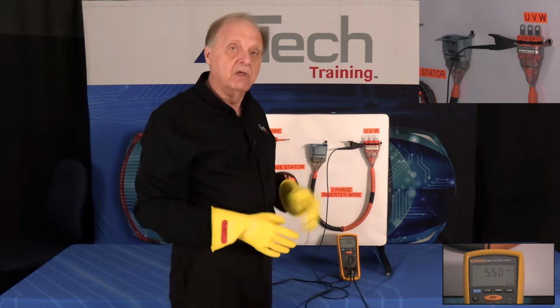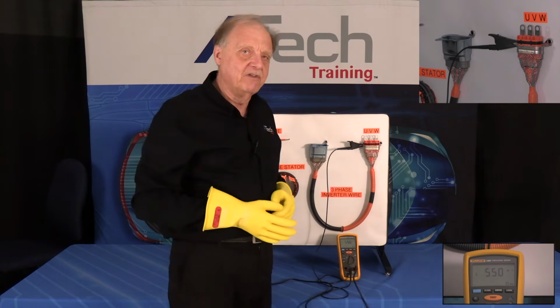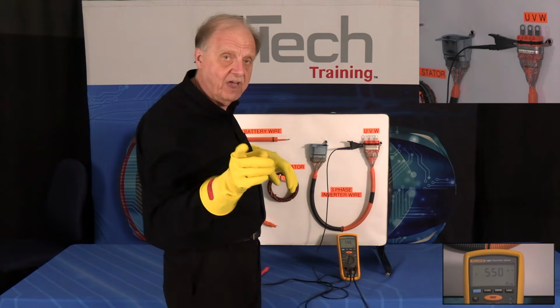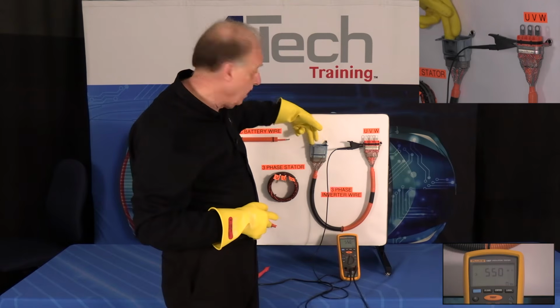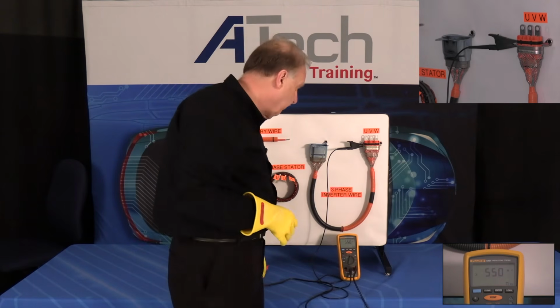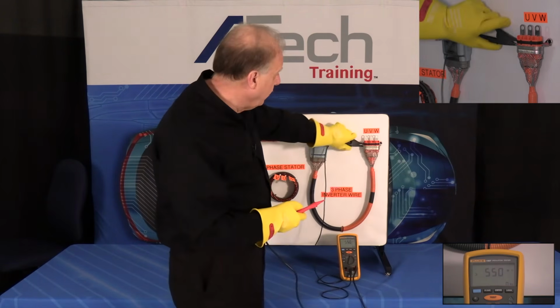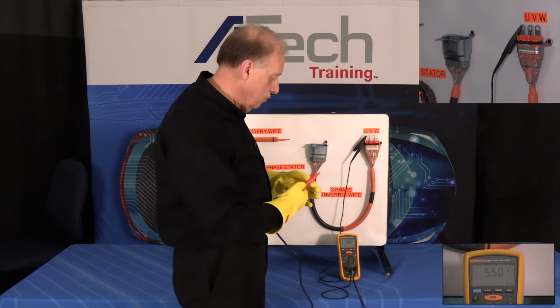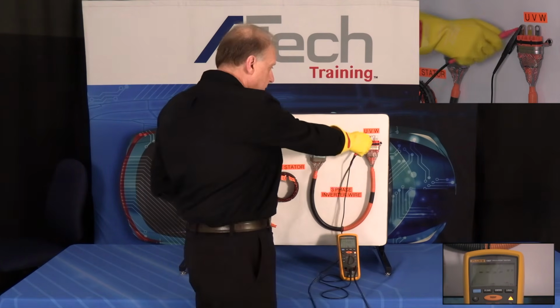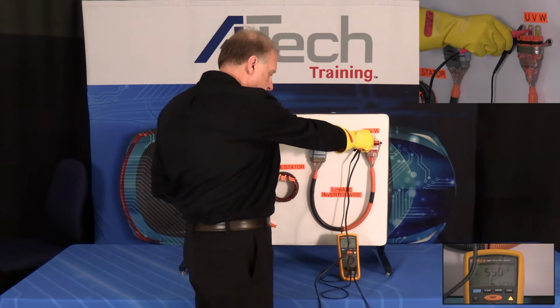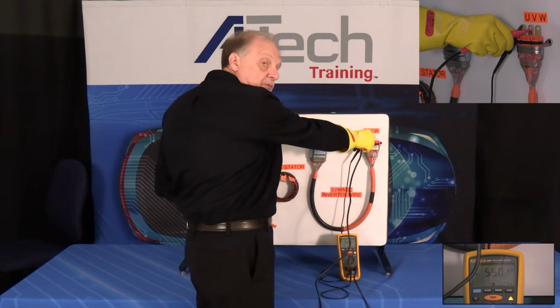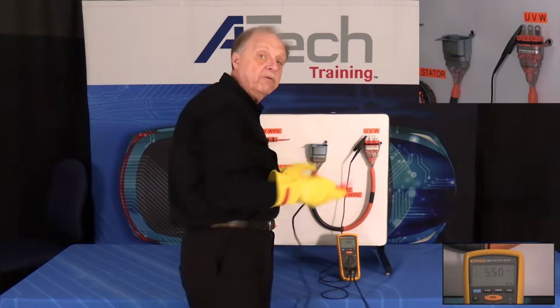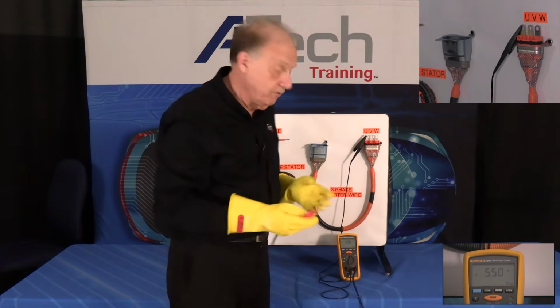So we were doing this one. We're just doing this on a board. I don't have to necessarily do that. Now I could actually check on the other end of the other connector here, check it again. Now the next thing I want to do is go between the U and the V. And notice again, got 550, so that means the system's good. That's what we would consider open. There's nothing there. There's no short to anything.